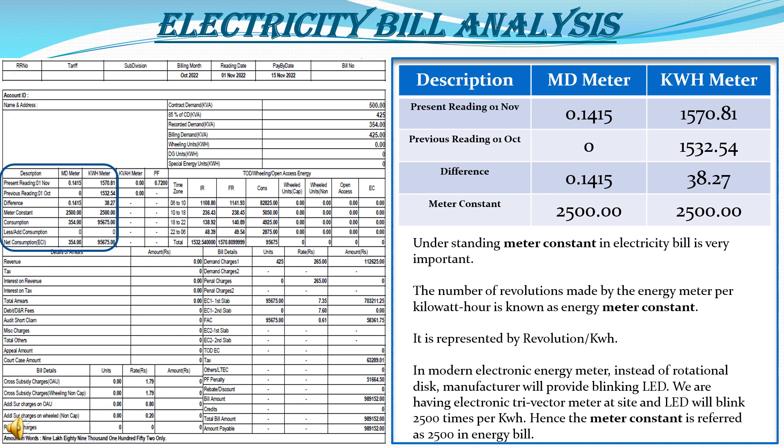The meter constant in both the maximum demand meter and KWH meter is referred as 2500. Understanding the meter constant concept in the electricity bill is very important. The meter constant is the number of revolutions made by the energy meter per KWH, known as the energy meter constant. Every energy meter has a constant — here it is 2500, represented as revolutions per KWH. In a modern electronic energy meter, there are no rotational disks, so instead the manufacturer provides blinking LEDs that blink 2500 times per KWH. Hence the meter constant is 2500 in the energy bill.